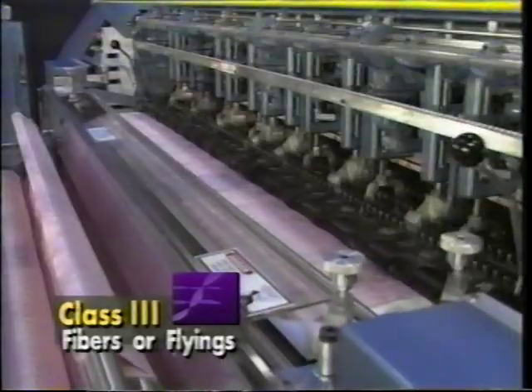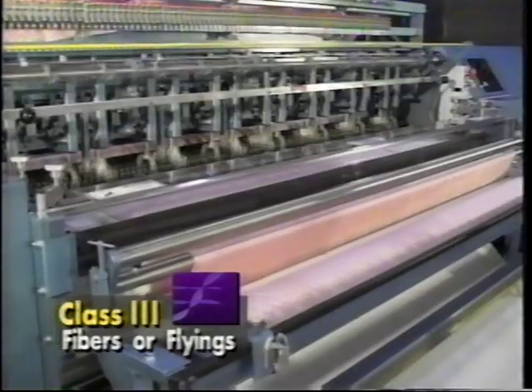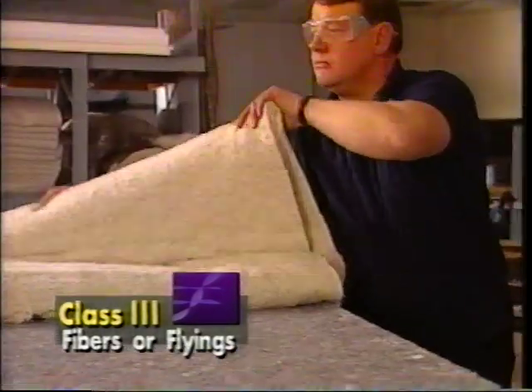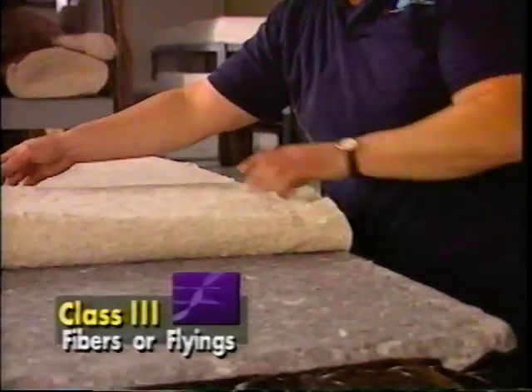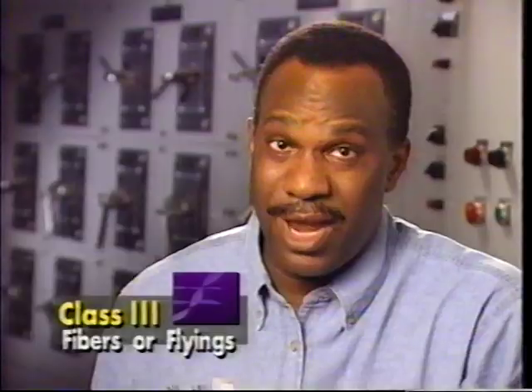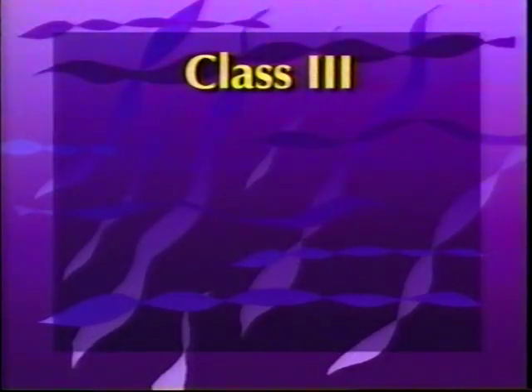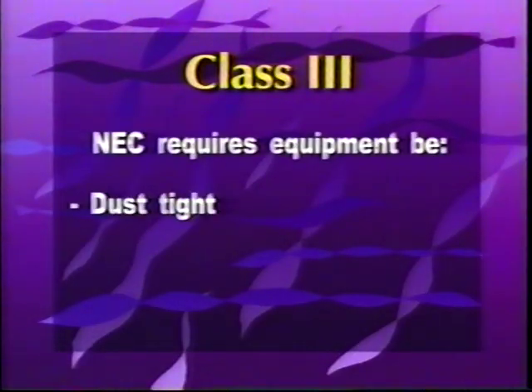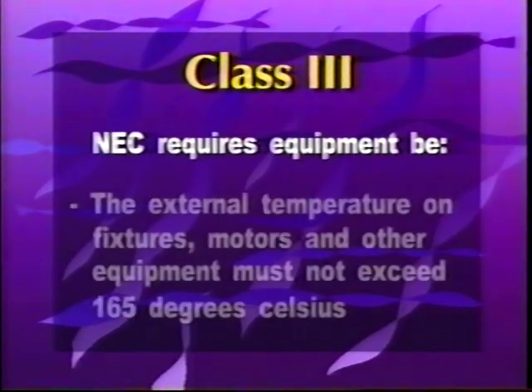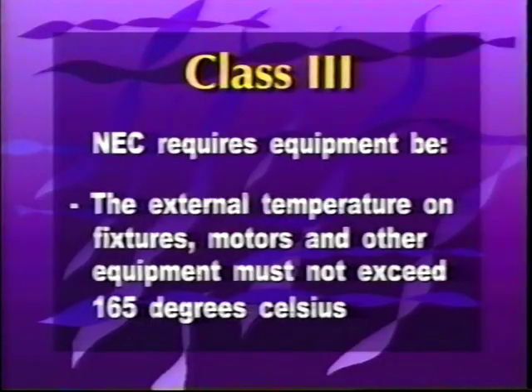A Class 3 hazardous location is any area where ignitable fibers or flyings are present. The main concern with fibers and flyings is the fire hazard created when they collect on equipment and cause heat buildup. Cotton and textile operations are good examples of Class 3 areas. Equipment in Class 3 locations must be dust tight, prevent the escape of sparks, operate at a temperature below combustion, and the external temperature on fixtures, motors, and other equipment must not exceed 165 degrees Celsius.